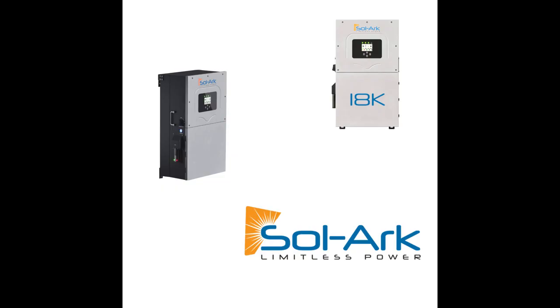So lastly, I just wanted to touch on the features before I hand it over to Josh here on the 18K and our new product. You can maximize your PV with this product, as in not only can you max out the 32 kilowatts of DC PV on the system, you can even add in additional AC coupled PV to max it at 40 kilowatts of output. We do have the highest surge rating off grid in order for those high HVAC loads, or maybe a 1.5 horsepower pump and above, as long as it's within the specifications for that locked rotor amperage, and we're able to provide that 32 kilowatt surge for 10 seconds. It's going to be a fantastic solution for those large loads.